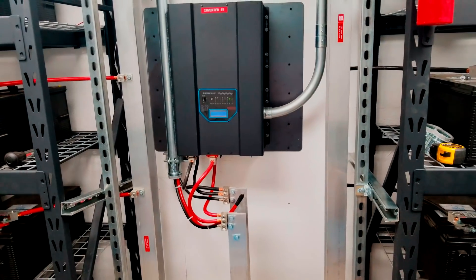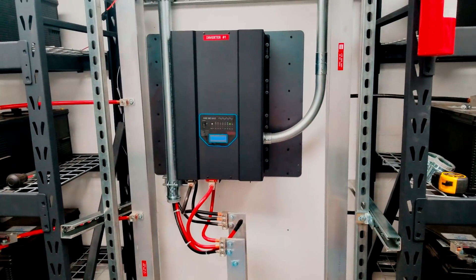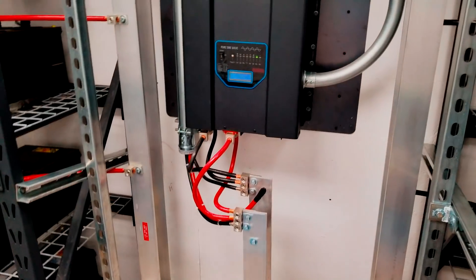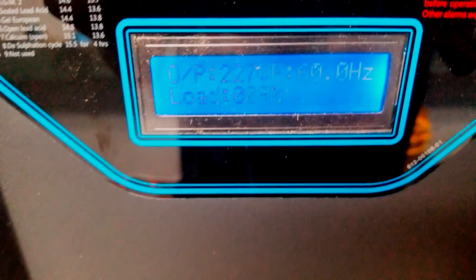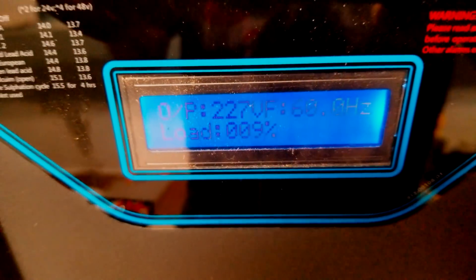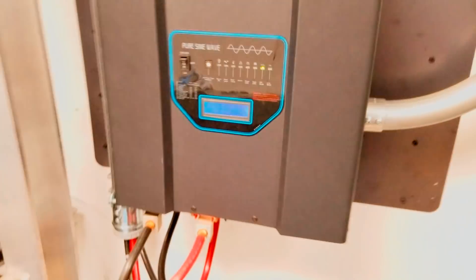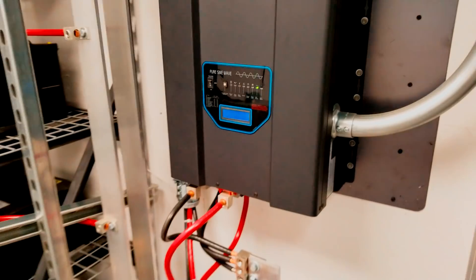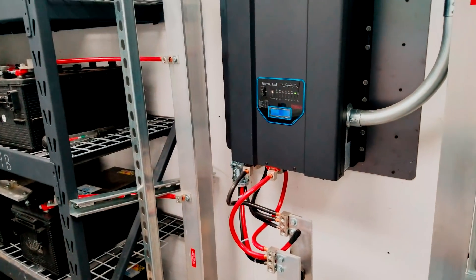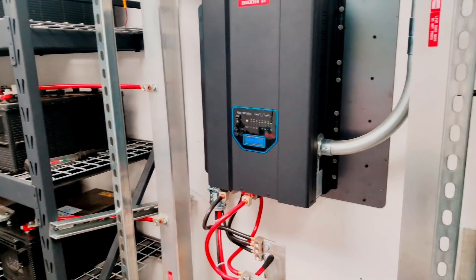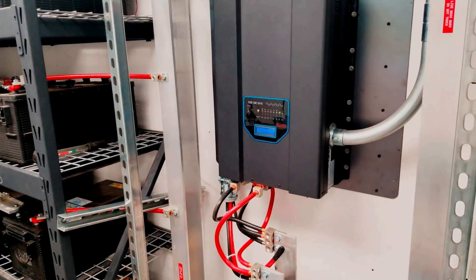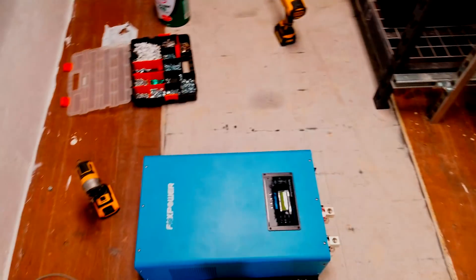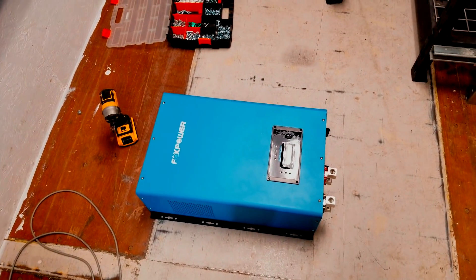One will only be on for the bulk of the time, but what I really like about this inverter is if you look on this one at the output voltage, it's 227 volts. So by the time you go any reasonable amount of distance, you're down around 220 somewhere in there, and that's too low for a lot of appliances to operate. This unit right here is around 240 to 242 volts, which is a lot more useful.